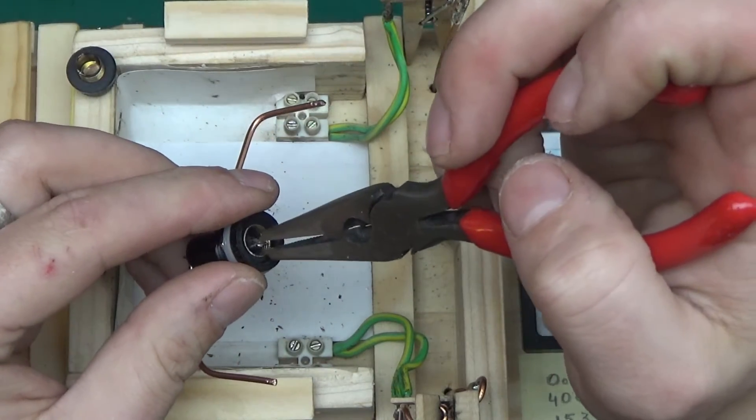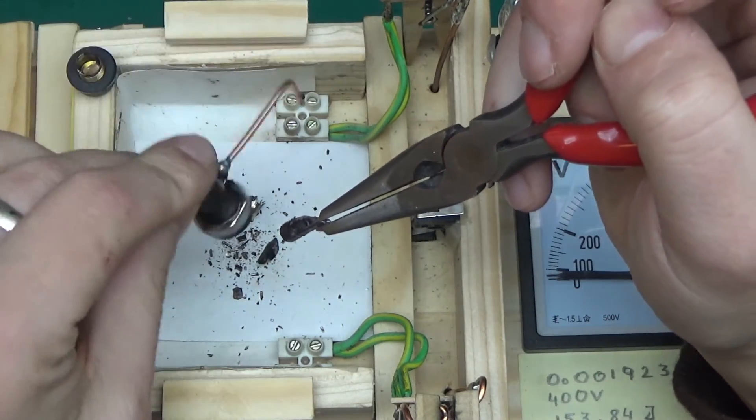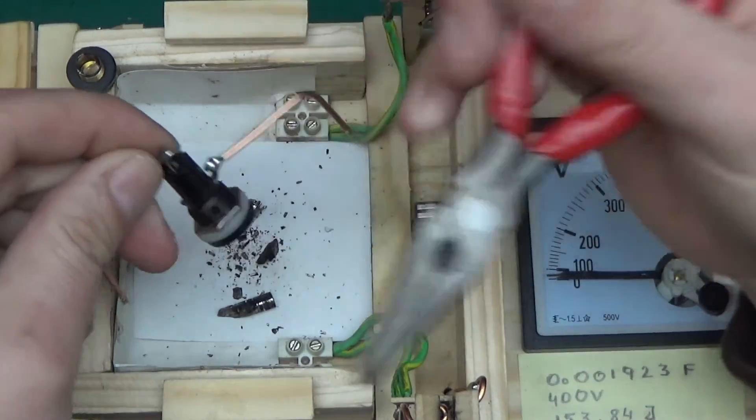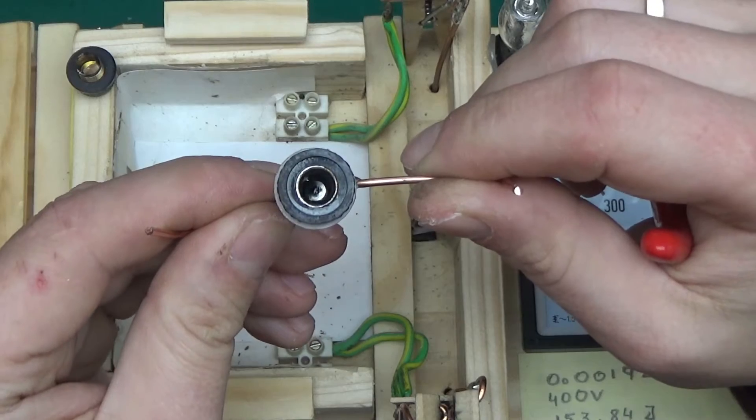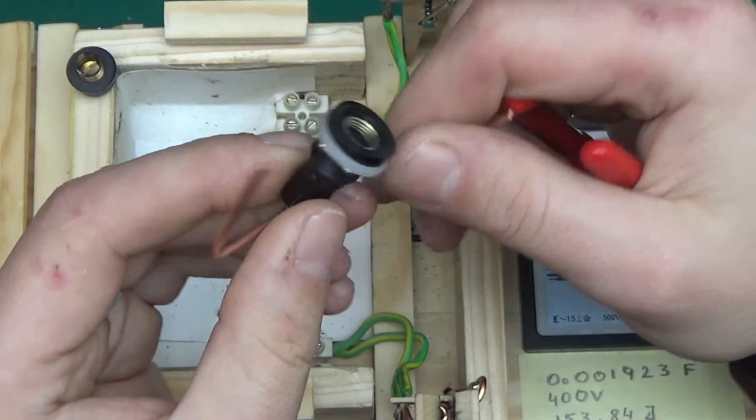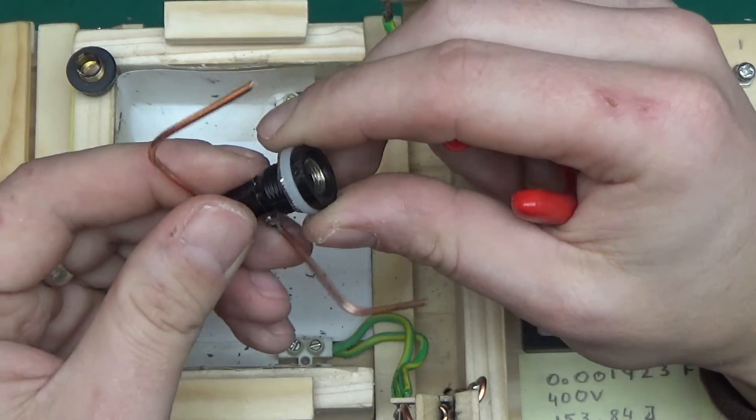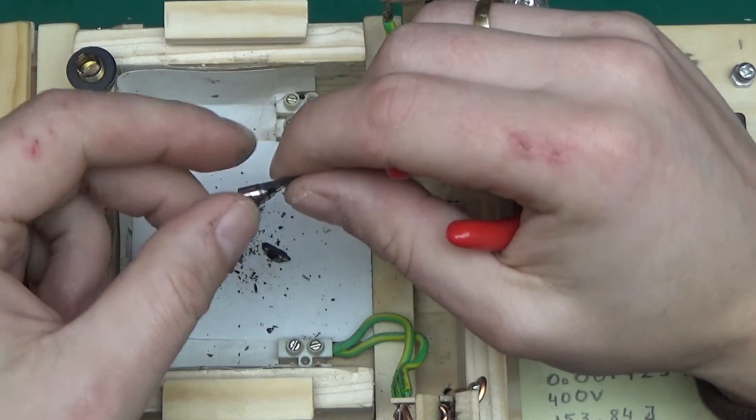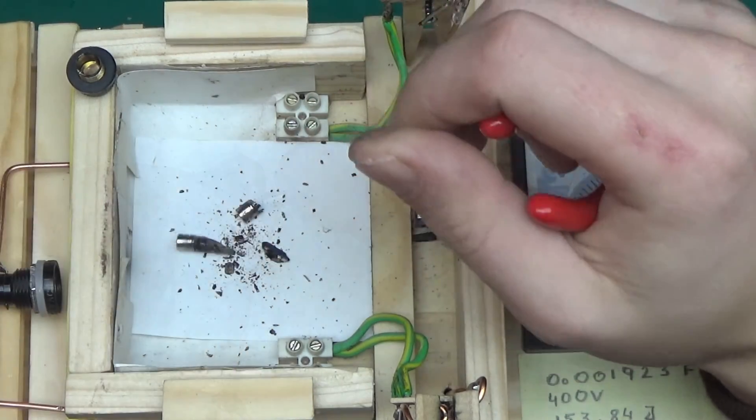Let's see if I can get the rest of it out. There's a little bit of charring on the contact of the fuse holder, but mechanically it's actually quite sound. It did hold up and contain that explosion inside. We did definitely get an explosion because the fuse is no more, but the fuse holder did quite well.